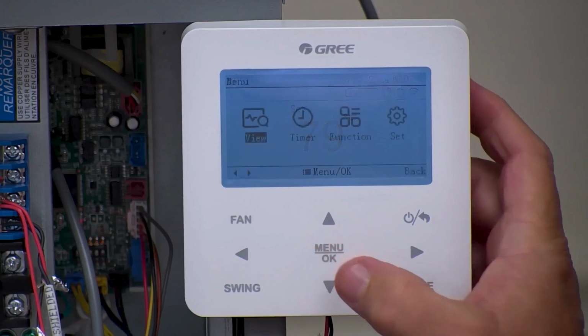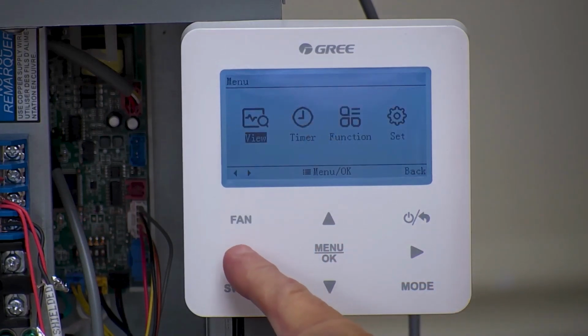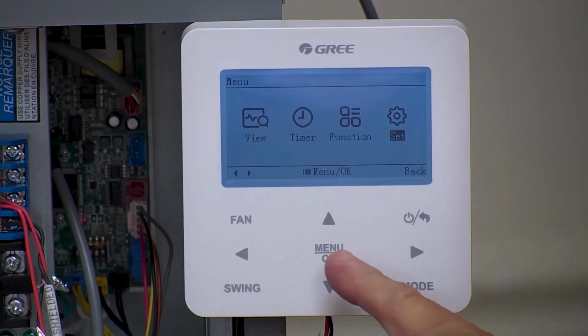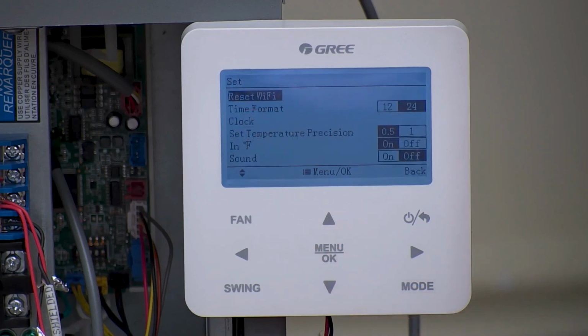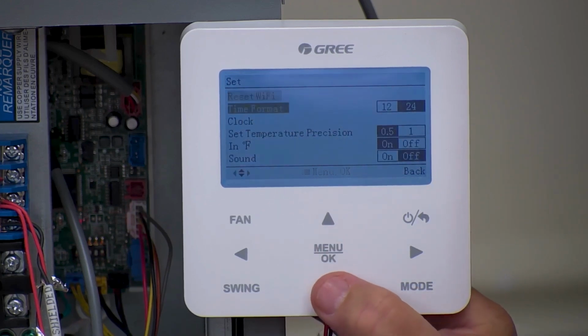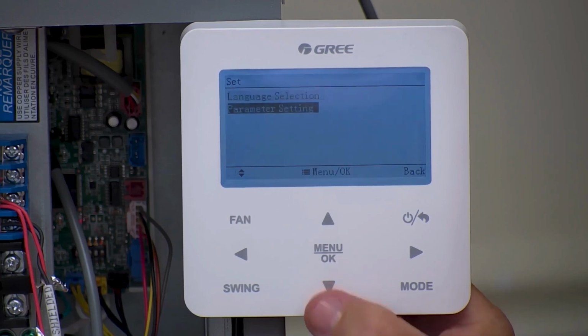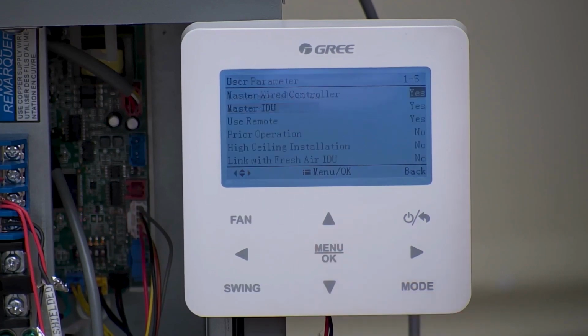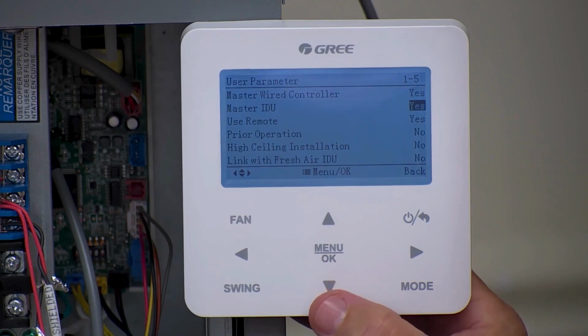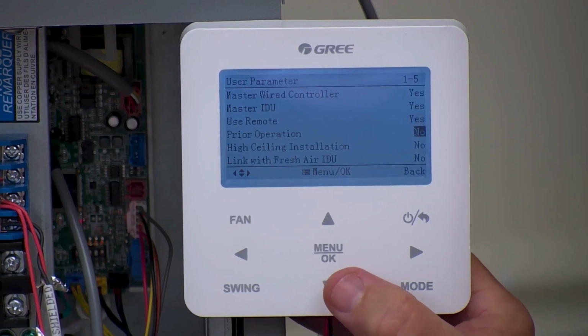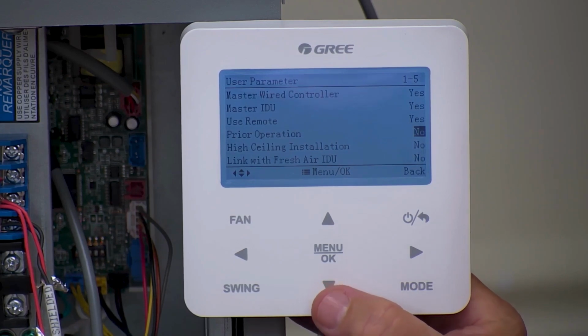So we go to menu, hit it one time. You can use the right or left arrow keys, go to set. We'll go here, and you'll have your typical settings that you have with a GREE wired controller. And then the parameter settings. So this is set up as master wired controller, master indoor unit, use remote, which means you can set this thing up where you can still use the remote along with the wired controller, or you can say, no, I don't want the remote to be able to function.